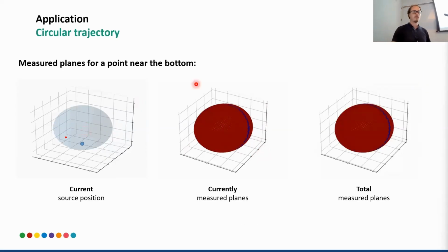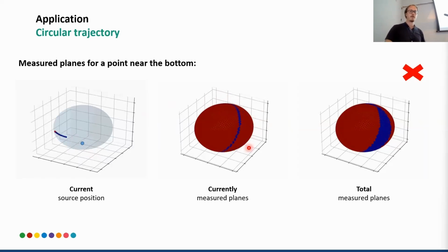However, if I move the region of interest to the bottom, then this X-ray is tilted, and analogously, the circle is tilted. And if we now rotate, we see that this tilted circle is rotated, and that therefore, yeah, directions are missing, and that's the reason for cone beam artifacts.